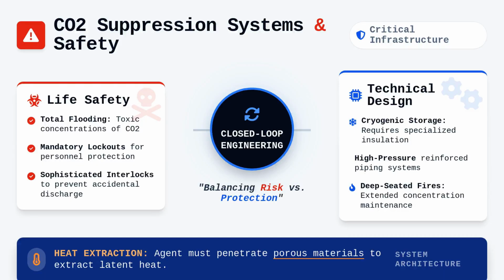Unlike clean agents, CO2 is often stored as a cryogenic liquid, requiring specialized insulation for high-pressure piping. You must treat the design of these systems as a closed-loop engineering problem where human life, equipment protection, and fire dynamics are weighed against the severe risk posed by the extinguishing medium itself.